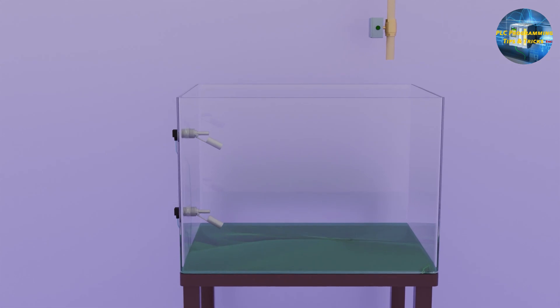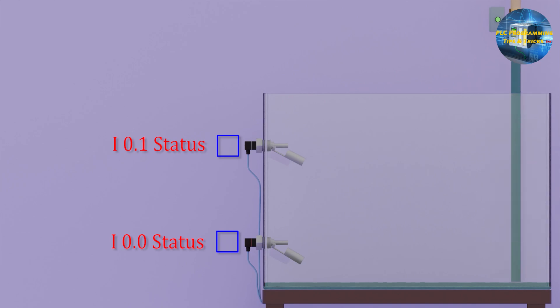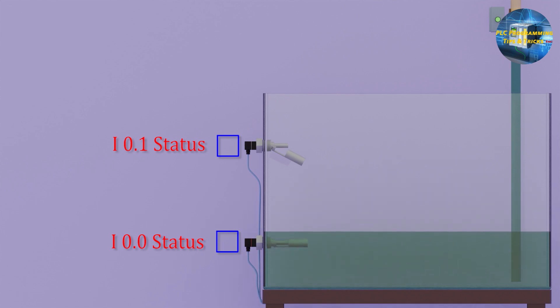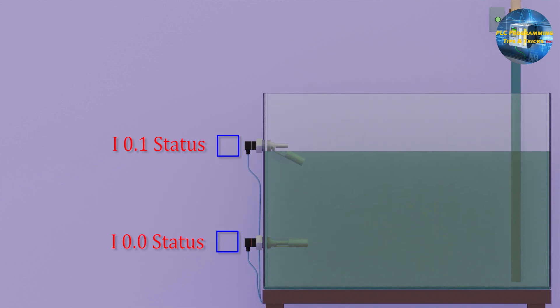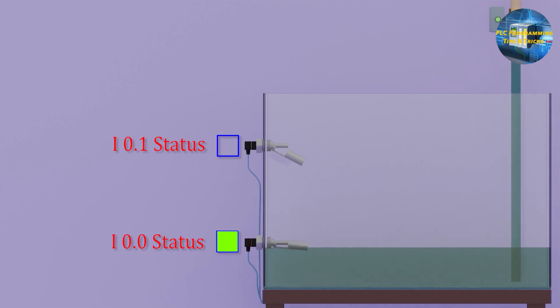First, let's see the setup for today's tutorial. We have a water tank with two level probes. The low level probe is connected at I0.0 input of the PLC, and the high level probe is connected at I0.1 input of the PLC. The water inlet valve is connected at Q0.0 output of the PLC. As the water touches the low level probe, it moves up and down a few times before stabilizing at the up position. The same happens when the water touches the high level probe.